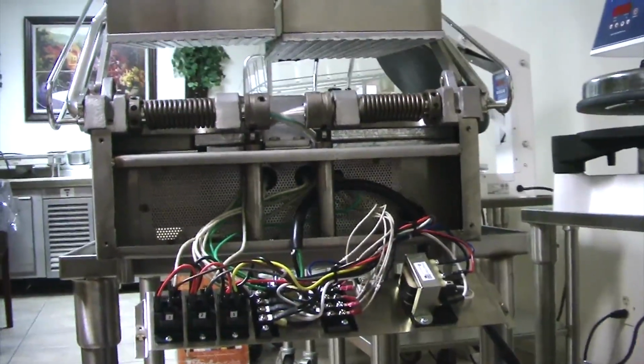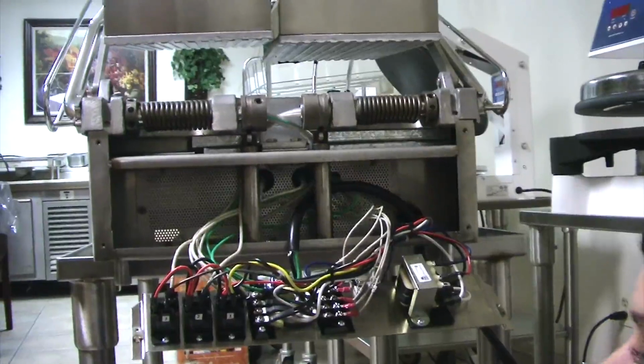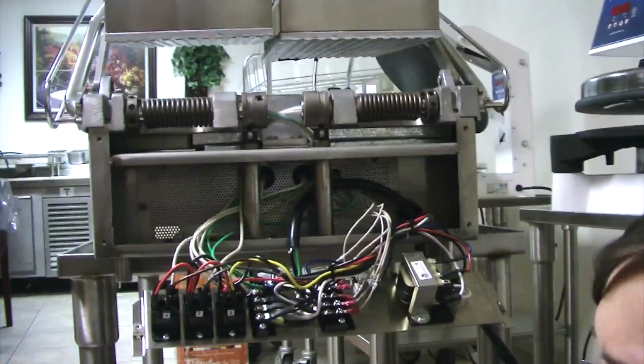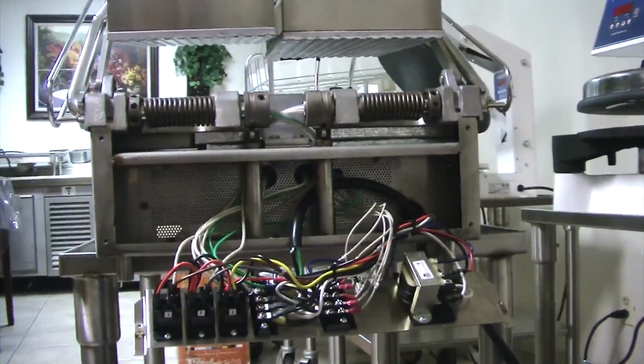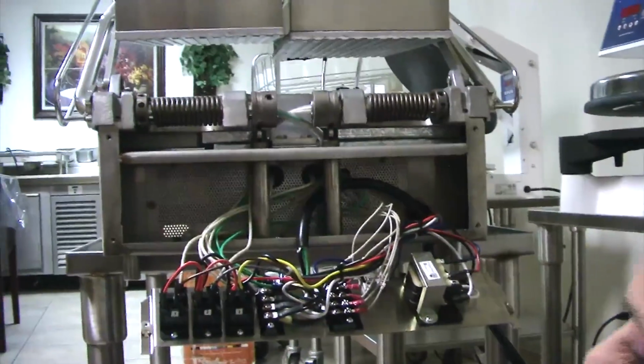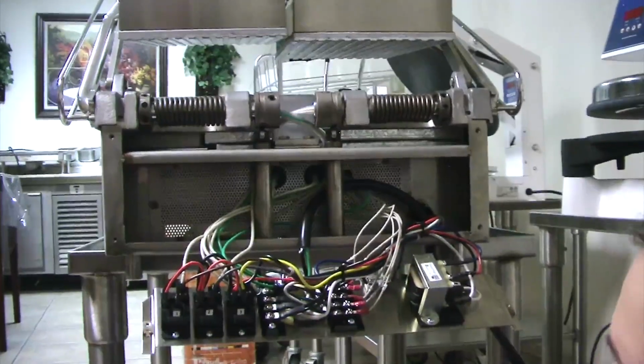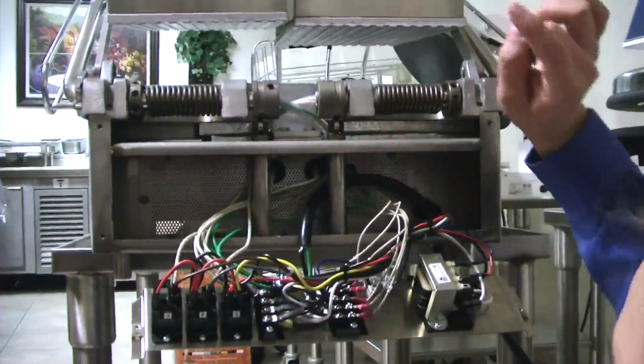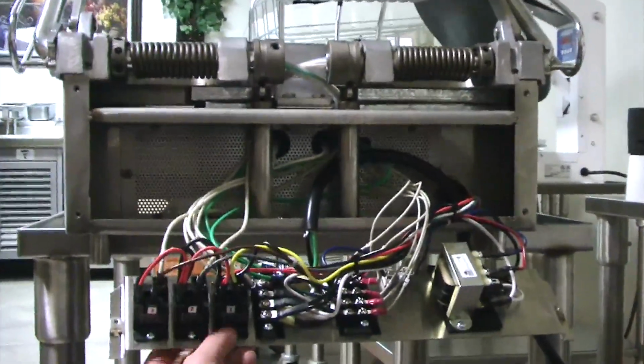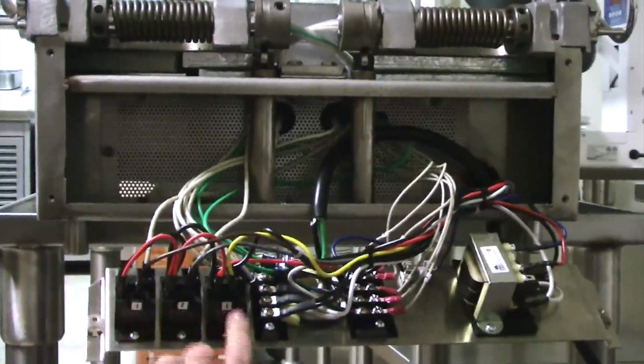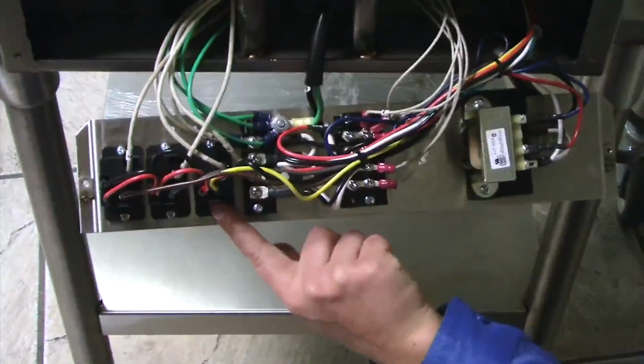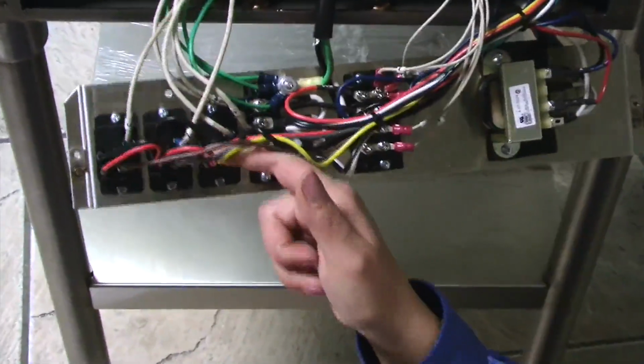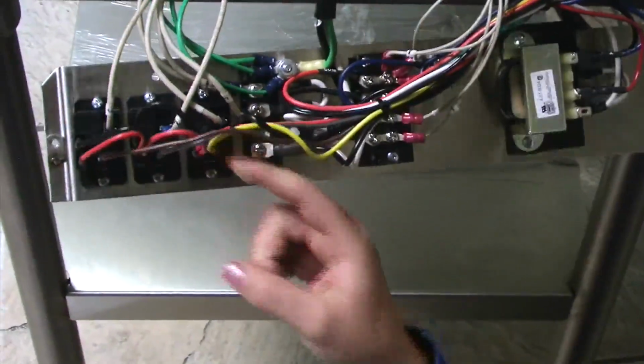Now, say you get a call where your bottom element is not heating to temperature and the bottom's reading 423 as the top are reading 525. You definitely want to come to the back here and check your number 1 relay. Number 1, number 2, number 3. Your number 1 relay here. Now you want to check your orange and yellow wire. These are coming from your control board, therefore it's going to read 12 volts DC.